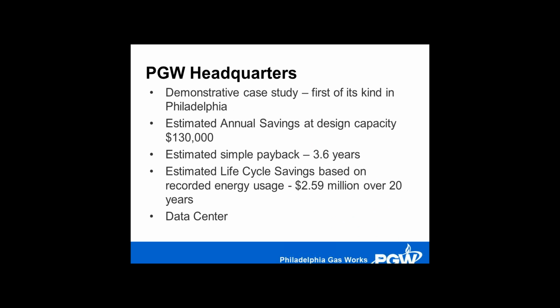When we started, we had a case study showing that a CHP system makes sense. After we finished, the estimated annual saving is $130,000. We have a plan to move our data centers to connect to our building, which will double the annual savings. The payback of the project is around 3.6 years, and the life cycle saving is $2.5 million over 20 years.